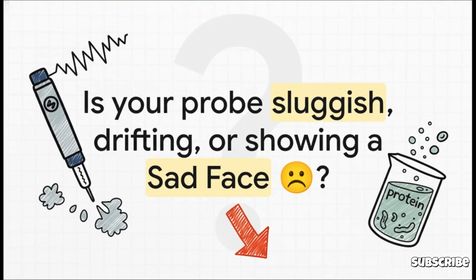So, is your probe acting up? Is it sluggish? Are the readings drifting? Is that sad face mocking you? This is a super common problem, especially if you work with what we call dirty samples, things like cell cultures or protein solutions. What happens is they leave this invisible film of gunk all over the probe's glass bulb. It's kind of like trying to read a book through a really greasy window. But the good news is there's a way to clean that off.